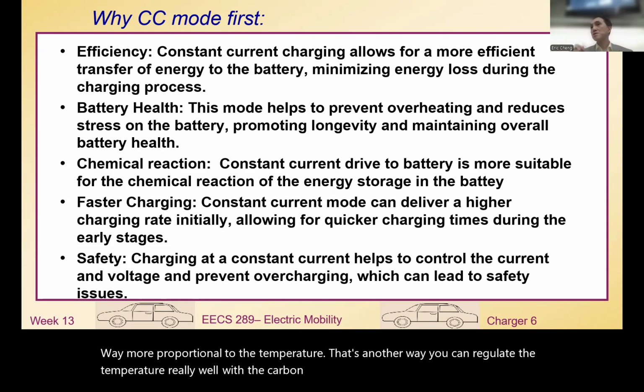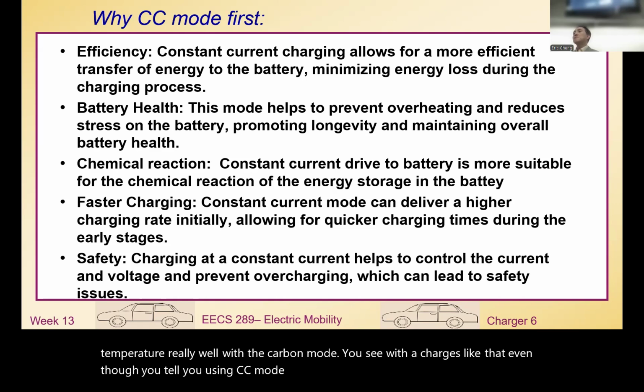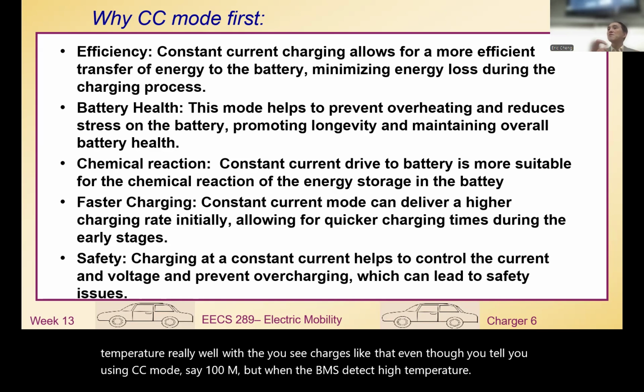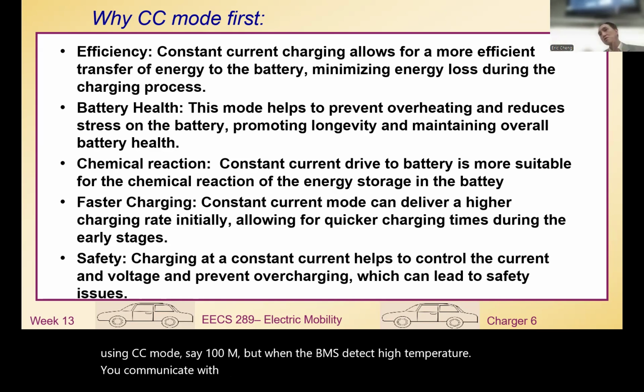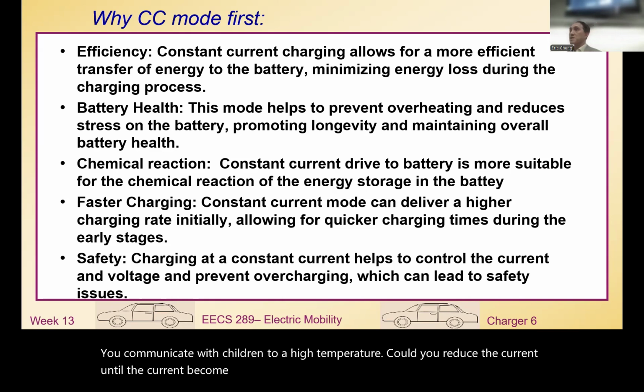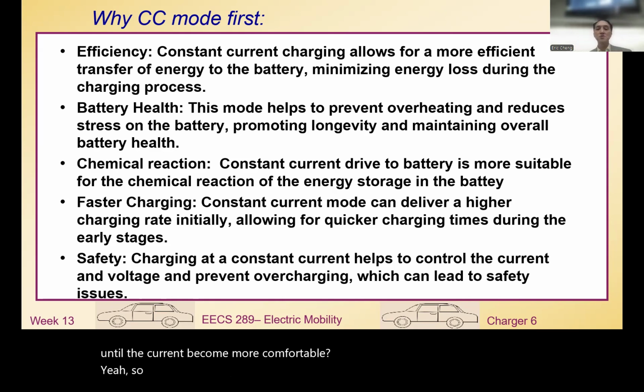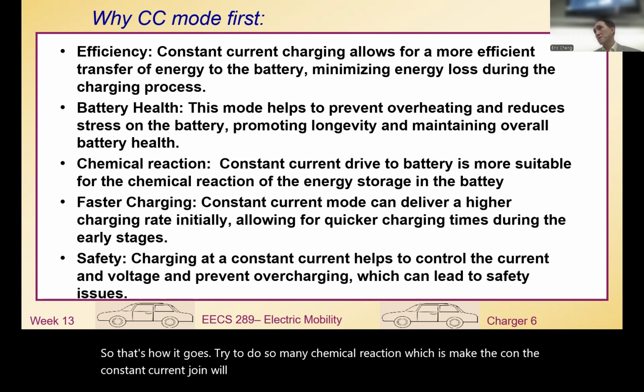With chargers like this, even if you set CC mode at say 100 amps, when the BMS detects high temperature, it communicates with the charger saying the temperature is too high, so the charger reduces the current until it becomes more comfortable. That's mainly about the chemical reaction, which makes constant current drive more stable—that's why we prefer CC mode.